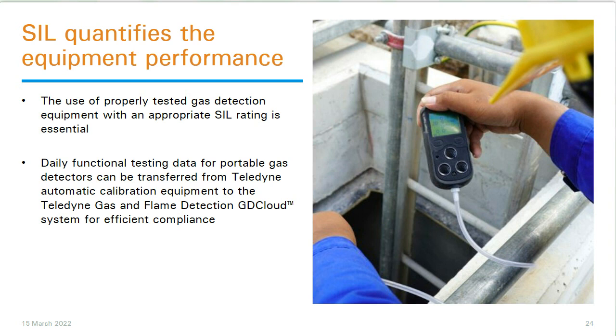When we look at portable gas detection devices such as the one in the photograph here, these kinds of devices are commonly calibrated, tested, bump tested at the beginning of a shift of operation and again at the end of a shift of operation by plugging them into calibration devices, desk-mounted devices. You just drop them into the device. And those calibration events are very, very important to record that that has taken place. A lot of legislation says that the equipment must be calibrated and that the data related to that calibration or testing must be recorded for regulatory purposes.